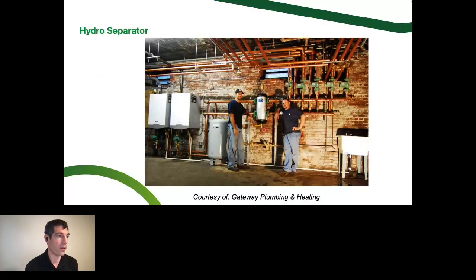That's one thing that can be really helpful in mechanical rooms that are getting smaller and smaller and smaller. I don't know if it's the case up in Canada, but I was a manufacturer's rep in Colorado for a while, and one of the tax law loopholes was that if you had a crawl space that was less than 5 feet and put the mechanical room in there, it didn't count as occupied space that you paid taxes on. So effectively what that meant in Colorado is the architects would jam all of this into a 4.5-foot crawl space, because then the owners didn't have to pay taxes on that space, which is just a crazy loophole. But in that case, it was very helpful to have a hydro separator just because there was less height needed to get it right, less space needed to put a hydro separator in there and have the proper performance of the system, even with limited vertical space.